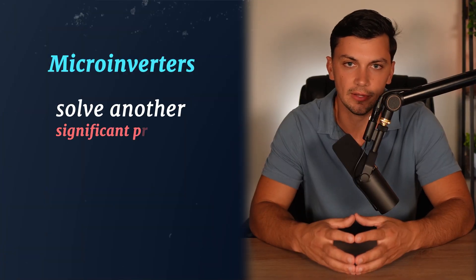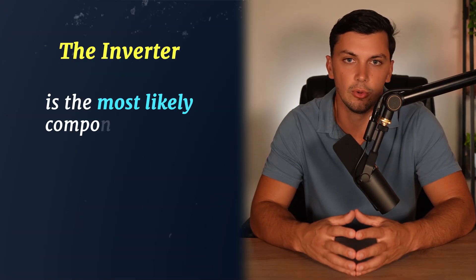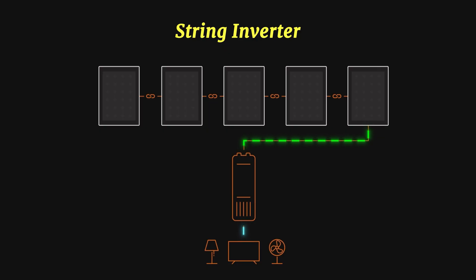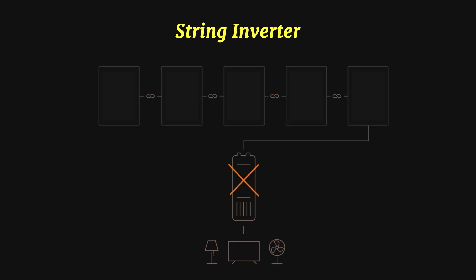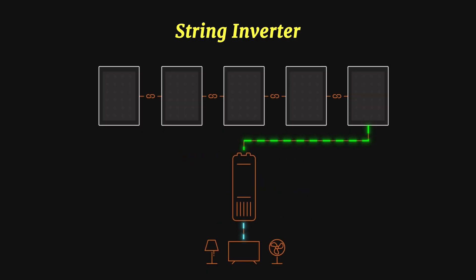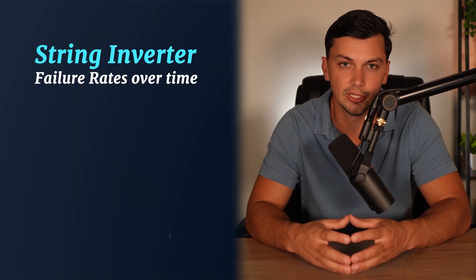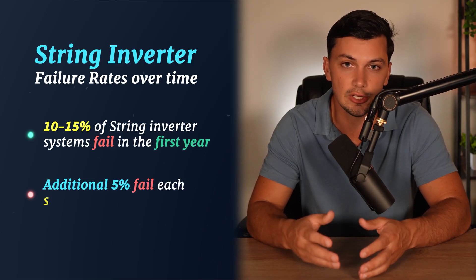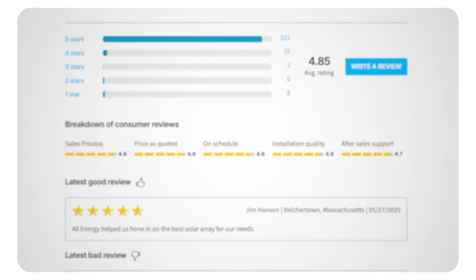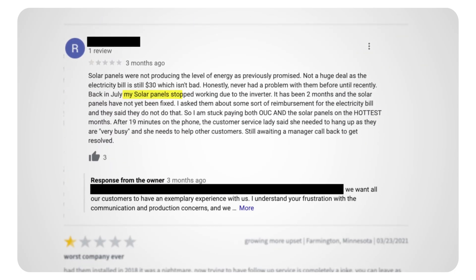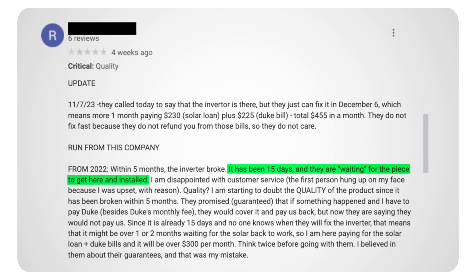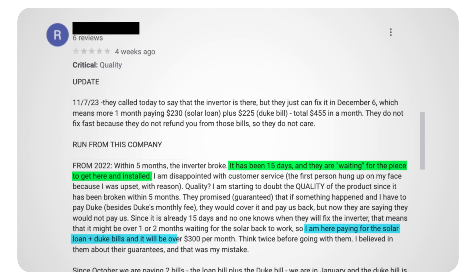Additionally, this approach solves another significant problem — a central point of failure. From all my years of working in residential solar, the inverter is the most likely component to fail within a solar system and can cause the entire system to stop producing power. This was a common frustration for homeowners with the traditional string inverter, as their solar panels couldn't produce power until that faulty inverter was replaced. On average and based on my experience, around 10 to 15% of string inverter systems fail in the first year, with an additional 5% failing each year after that. Many homeowners report waiting weeks for a replacement to be ordered and reinstalled, leaving them without solar production the entire time — which they still have to pay for.